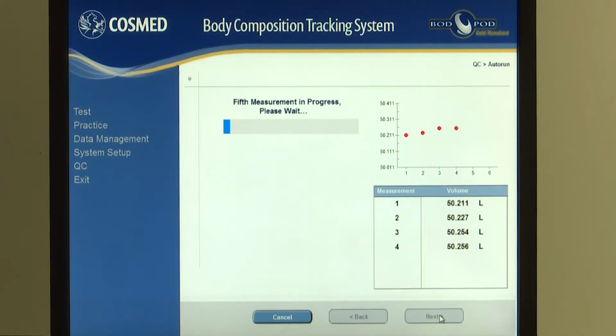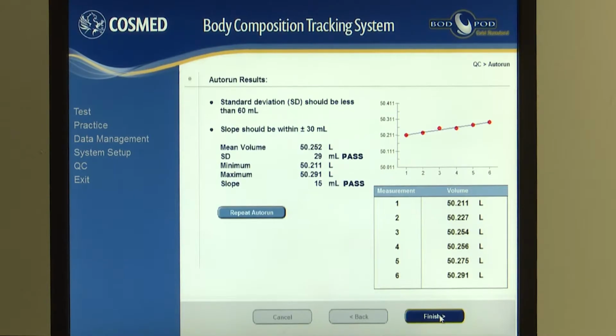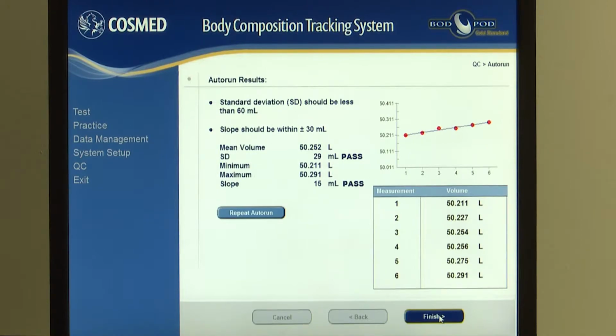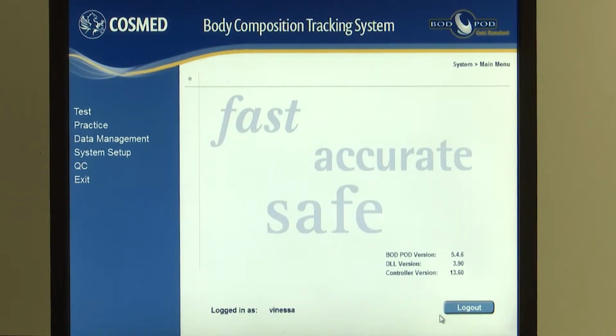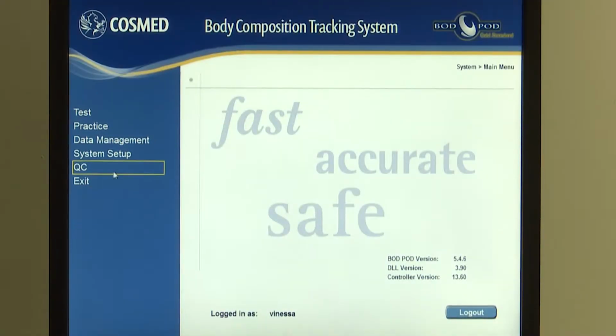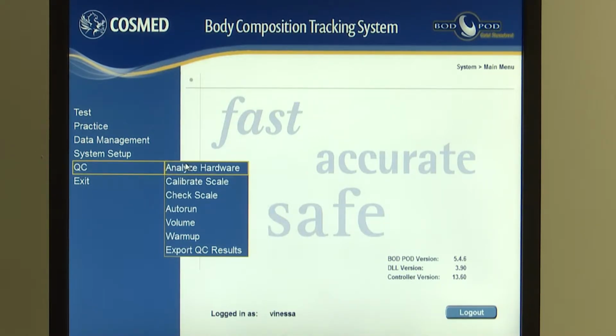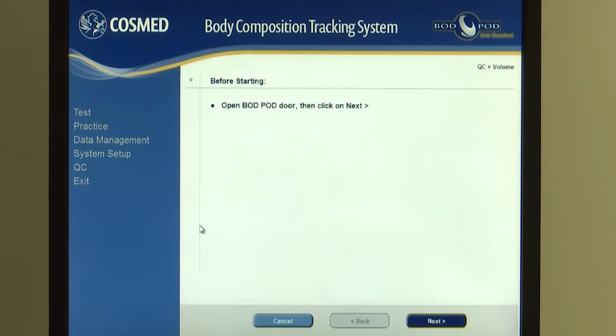After the auto run is complete, the screen will indicate if the auto run was a pass or fail. If the test fails, it must be repeated. If it passes, go to the next step. The standard deviations are listed on the screen as well. Go back to the QC tab, open the drop-down menu, and click Volume. Continue to follow the prompts on the Bod Pod computer screen and click Next after each step.